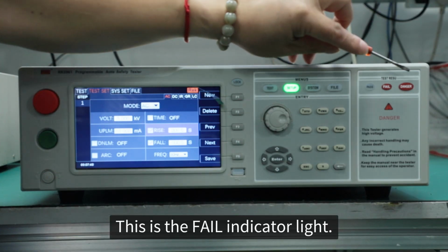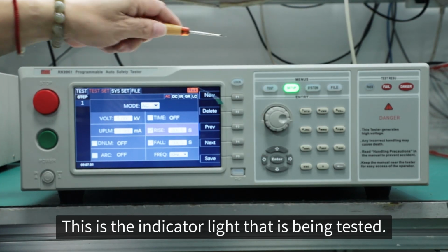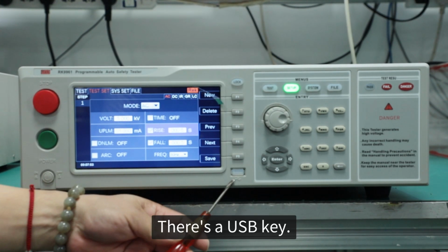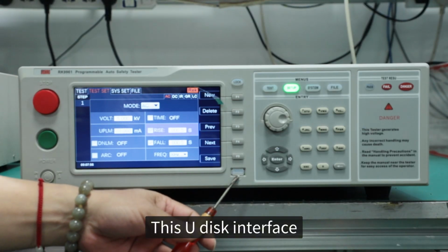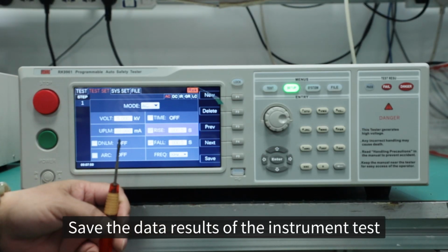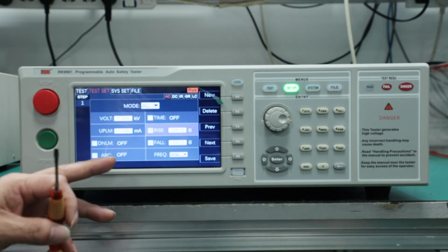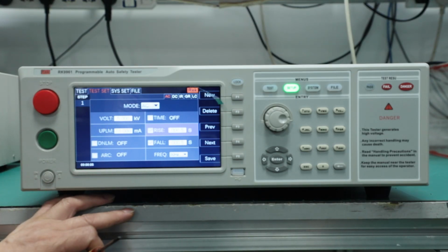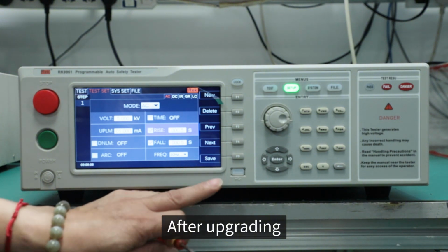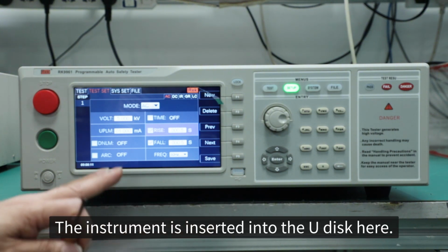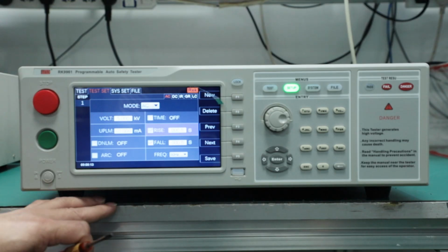This is the pass light. This is the fail indicator light. This is the indicator light that shows it is being tested. This is the entire front panel. There's a USB interface, this U-disk interface. If you want to save the data results of the instrument test, insert the U-disk here. The test results can be saved.